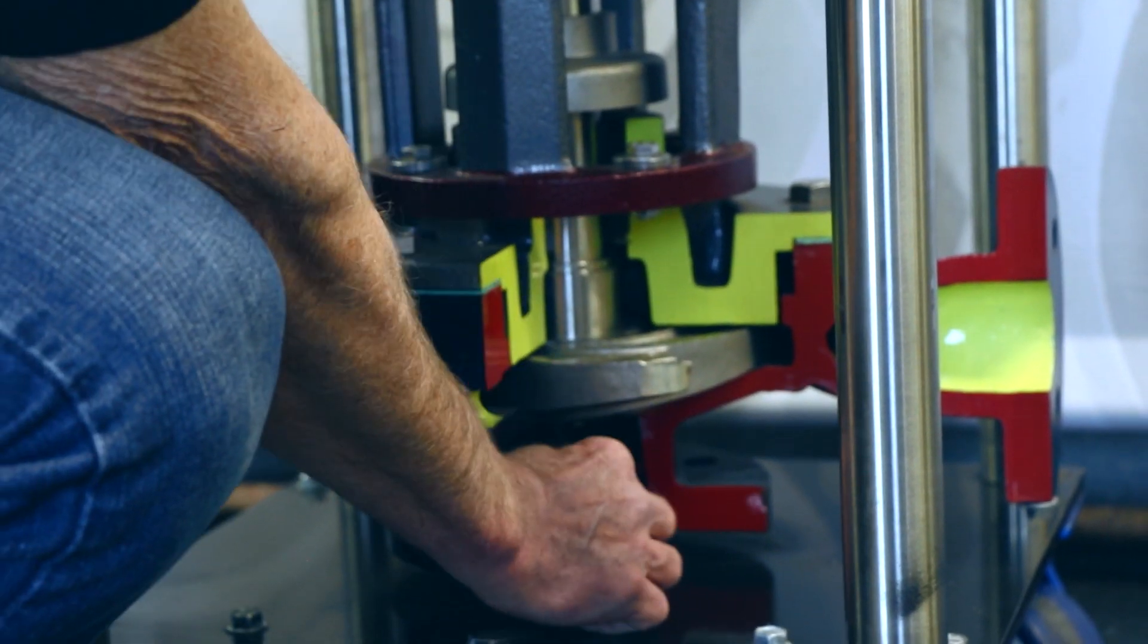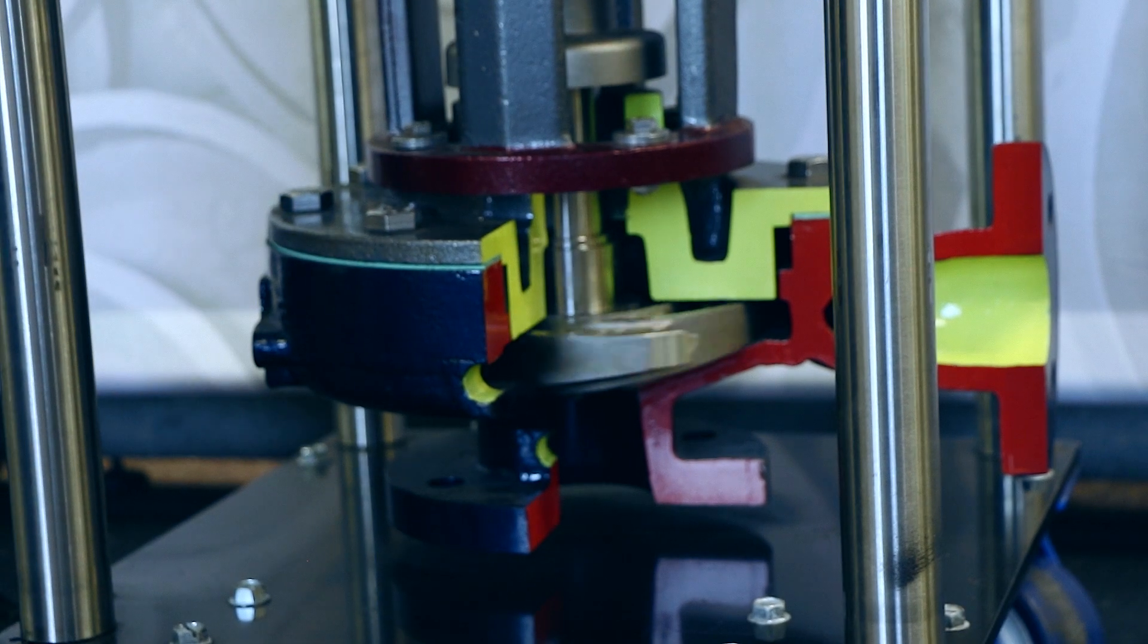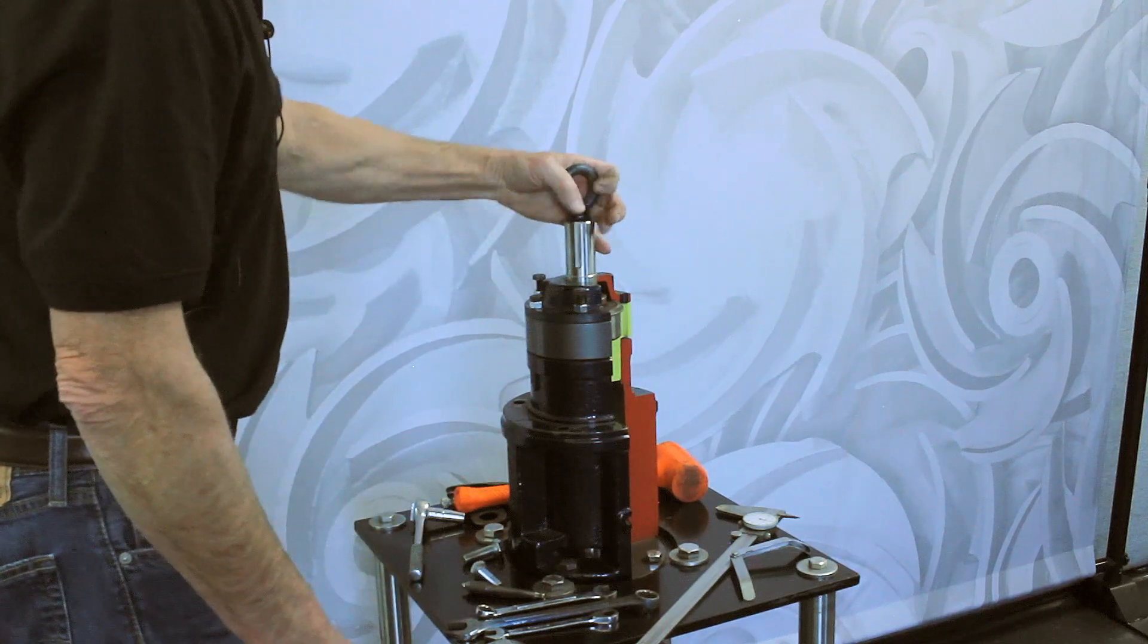You check your 20 thousandths by coming in through the intake on a live pump, but you can check your 20 thousandths right there with the feeler gauge. So that's set. You should be good to go on that.